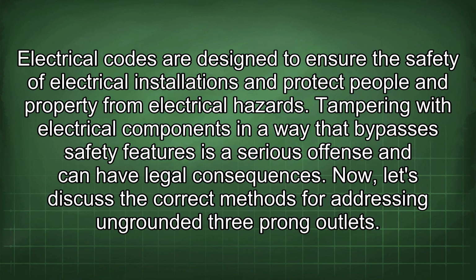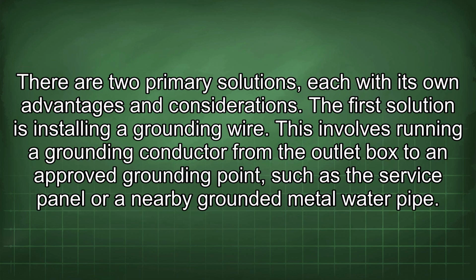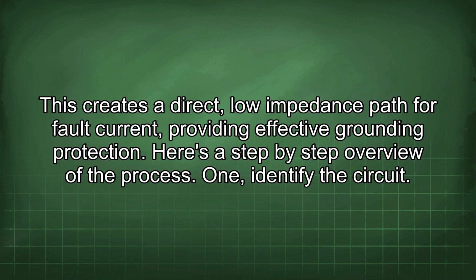Now, let's discuss the correct methods for addressing ungrounded three-prong outlets. There are two primary solutions, each with its own advantages and considerations. The first solution is installing a grounding wire. This involves running a grounding conductor from the outlet box to an approved grounding point, such as the service panel or a nearby grounded metal water pipe. This creates a direct, low-impedance path for fault current, providing effective grounding protection.